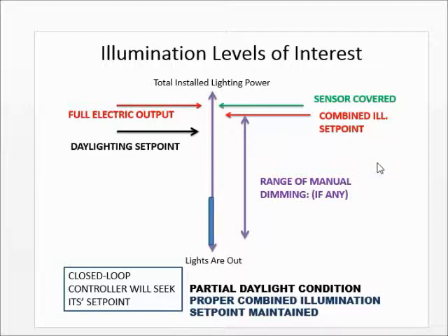And in the case of the little LS301 that we're looking at, simply cutting the power to it and restoring it will actually put it back into proper daylighting action. So that would be considered to be a temporary override, provided that when the room becomes unoccupied, it cuts the power to that LS301. So something like that. Also, hitting any of the other buttons on the area control might put it back into automatic operation. So this, while it is a design violation in the code, is not an acceptance testing violation.